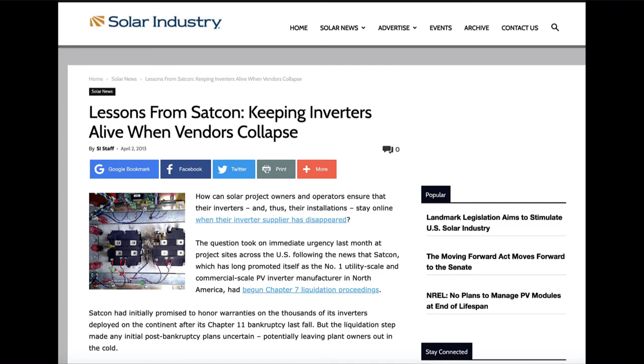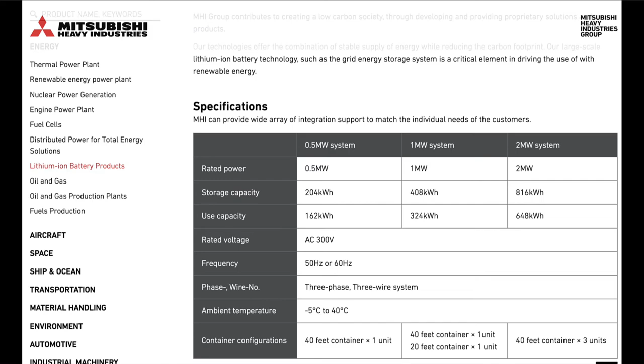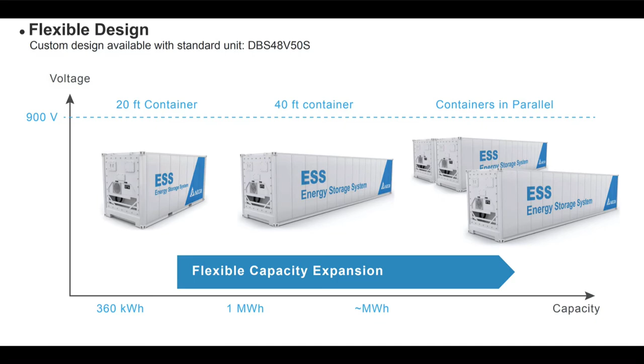So like a container battery, was that like something around half a megawatt? Yeah, megawatt, probably. So if you had a container battery that was a megawatt, you might fit four of those on a transformer? You could - you're cramming those containers together, you're going to have a lot of medium voltage transformers in a smaller area, especially compared to a PV system. Oh absolutely, yes. If the facility is dedicated to storage, that's going to be a much, much smaller facility - more like a substation type of facility. It's just going to be a glorified substation with storage in it. Essentially, that's what they look like.